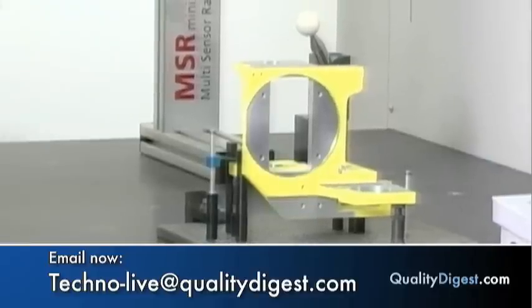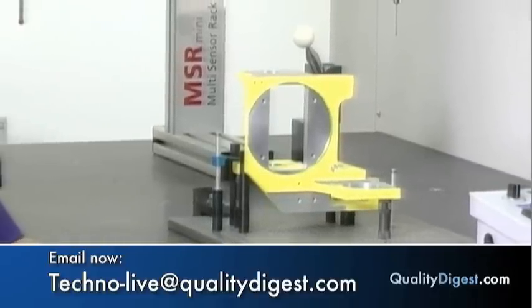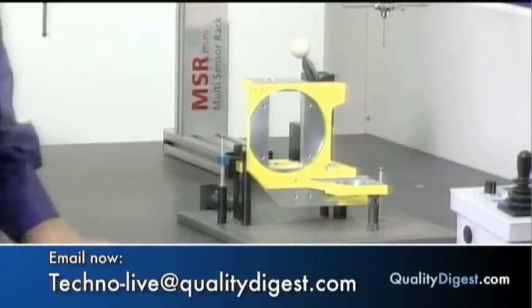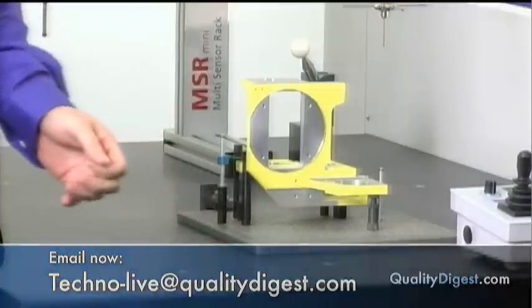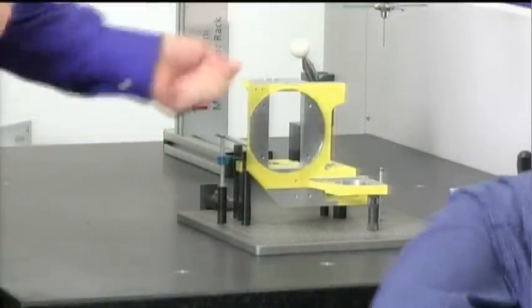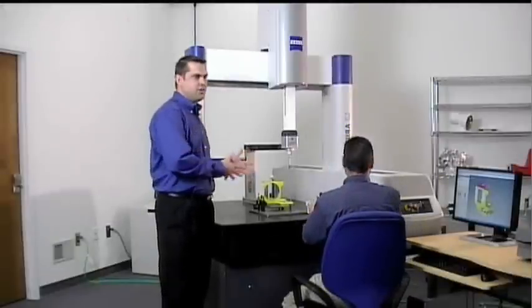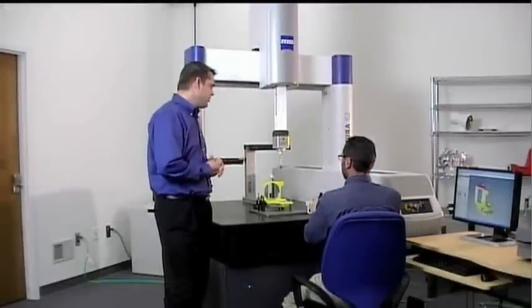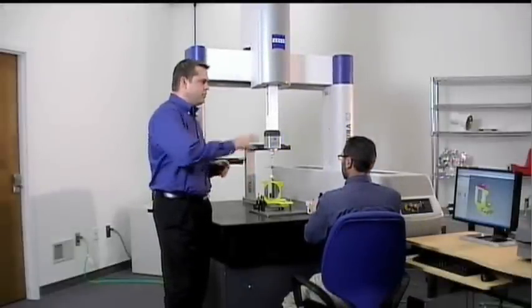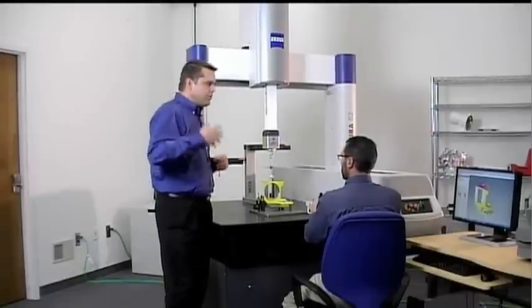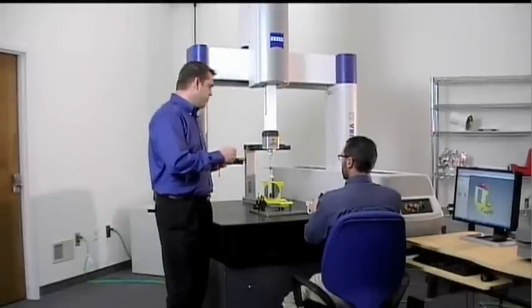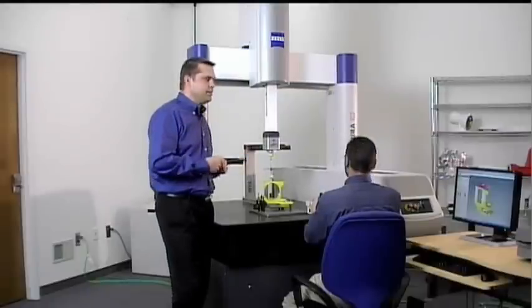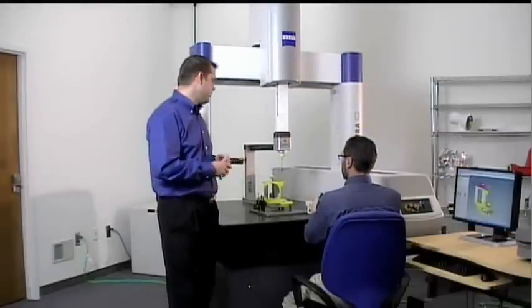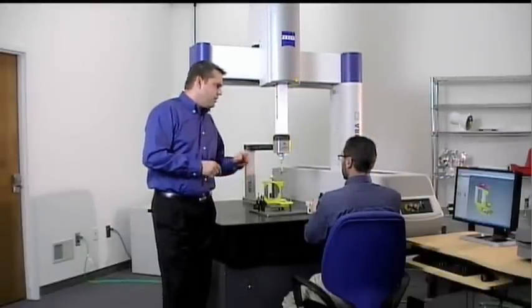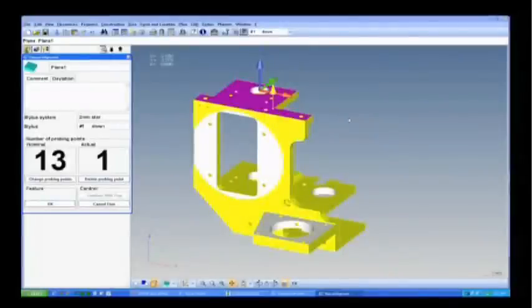So Scott, go ahead and take it from here. So I've come over here. We have a ZEISS Contura G2 model. And I've just put my part here in a fixture, and I'm going to ask Mick here to just manually align the part. The CMM needs to obviously know where this part is before it's executed. So if you look in the software, similar to the arm, it's actually prompting Mick here what surface needs to be measured to do this alignment. So as Mick goes through this, it's going to take about a minute or so.